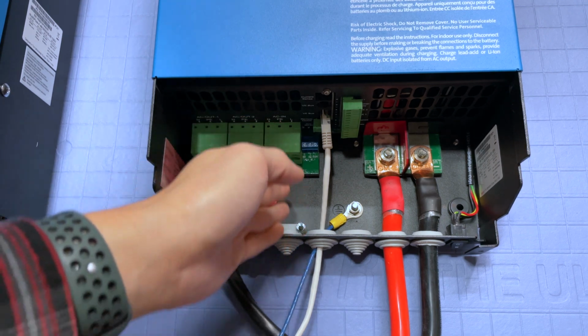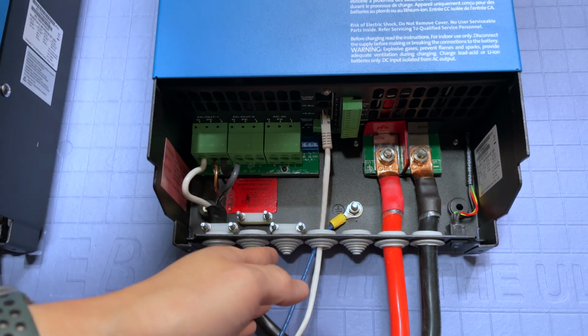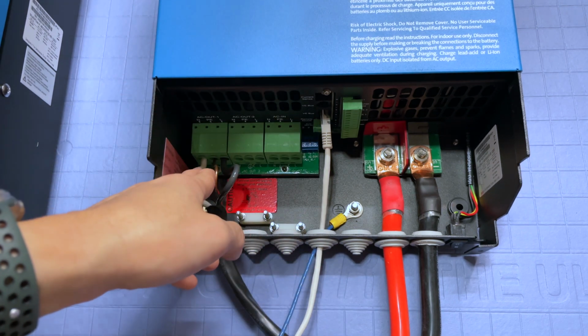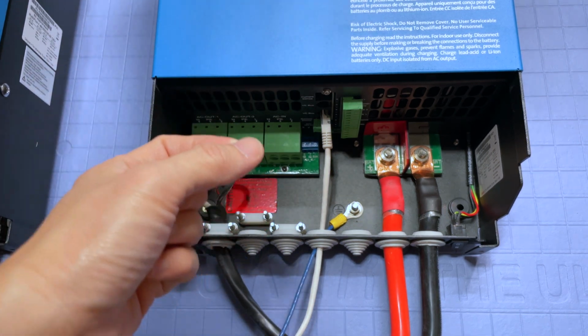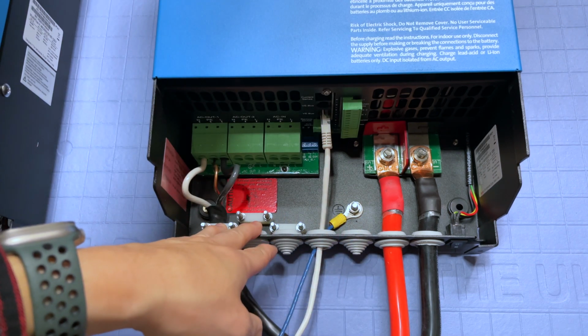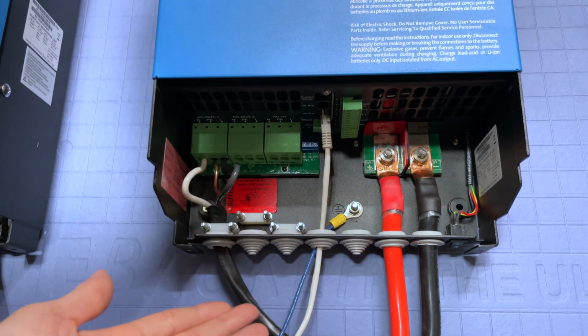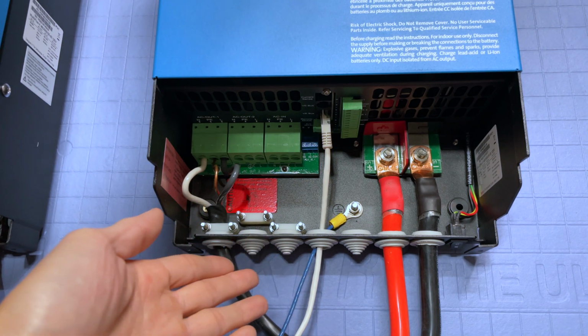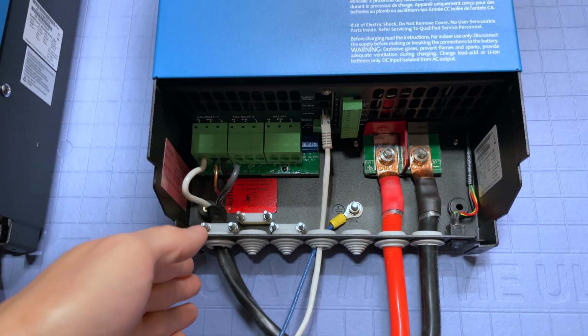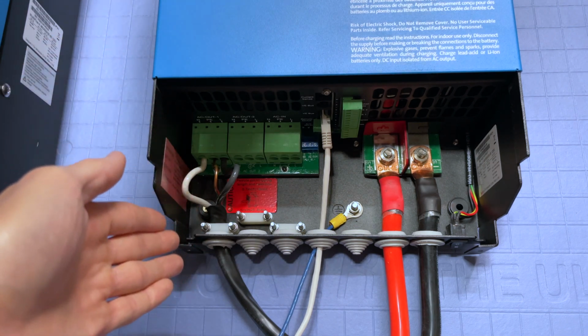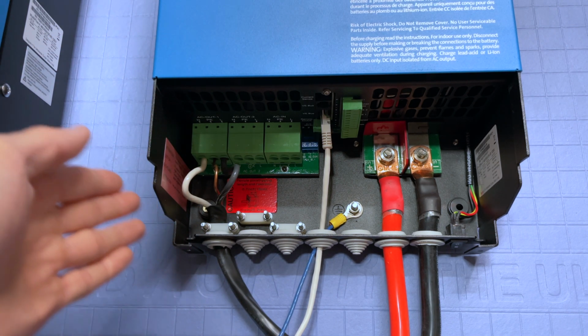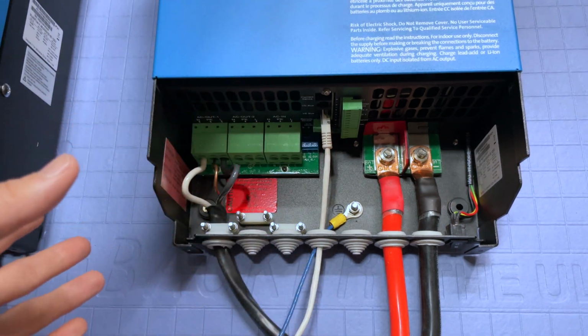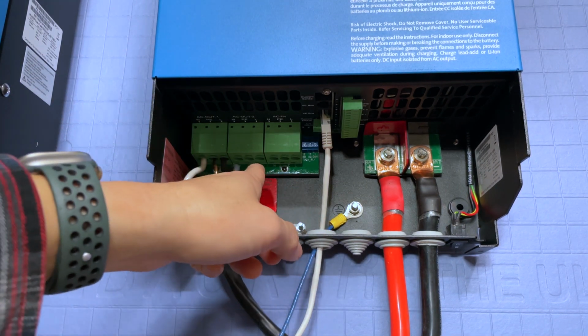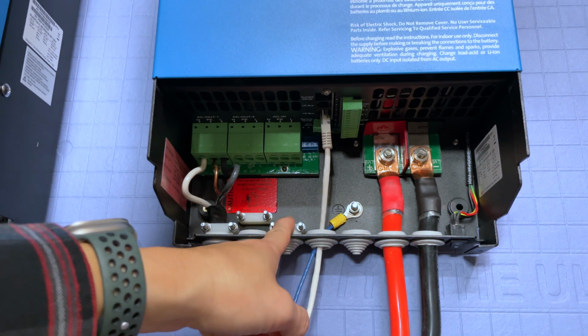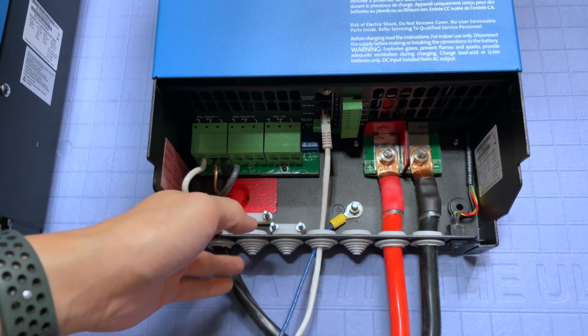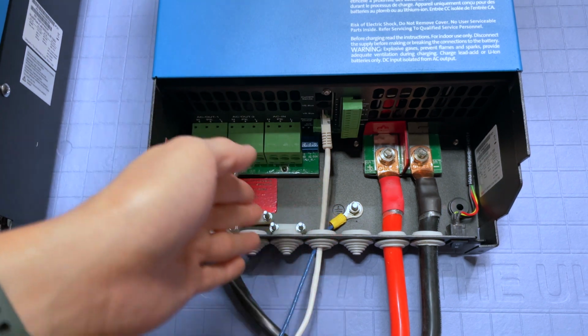But when power is no longer available, the automatic transfer switch built into here transfers the AC1 circuit only to be powered by the inverter. So it's pretty much like a UPS unit if you've used them before. If you look on the back, there's what they call surge only, and then there's another chain of circuits which are battery backup. That's pretty much exactly what's happening here, except on a much larger scale, mainly because AC2 out is not powered when AC in has no more power, and AC1 is always powered whether you have AC power or not.